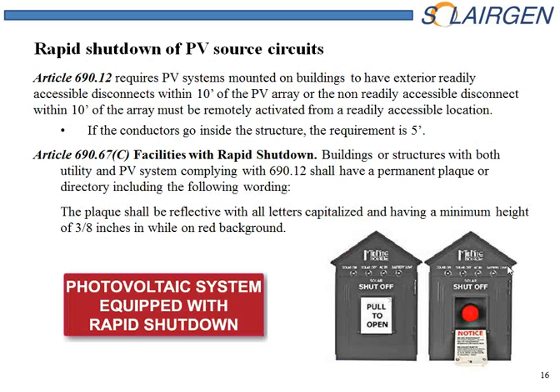It's a new requirement in the 2014 code for rapid shutdown. This is to maintain low voltage away from the PV array. The 2017 code is going to push it even closer to the PV array. Right now it's 10 feet from the PV array if it's on the exterior of the building, and 5 feet if it goes into the interior. So there actually has to be a contactor of some sort that would disengage all the conductors and reduce the voltage of the PV array.